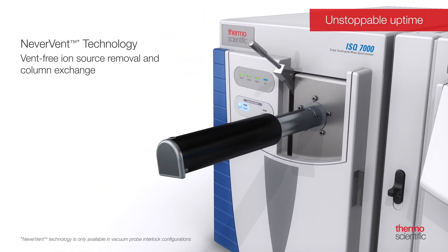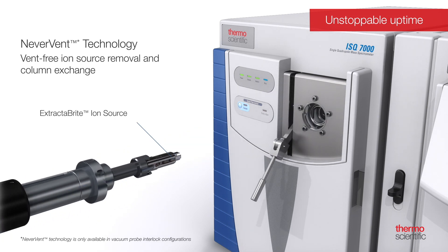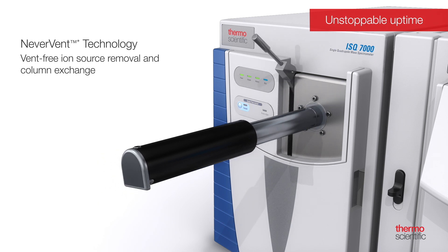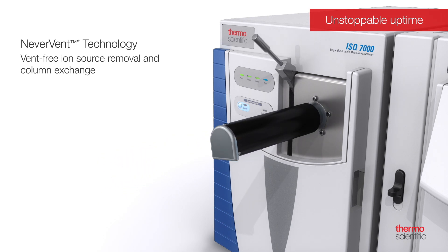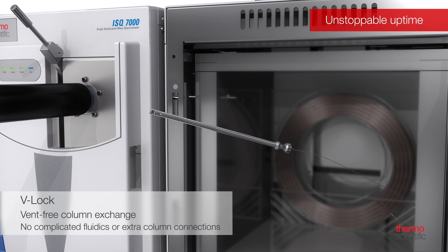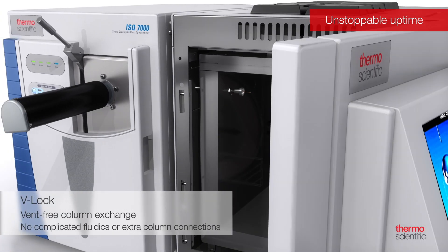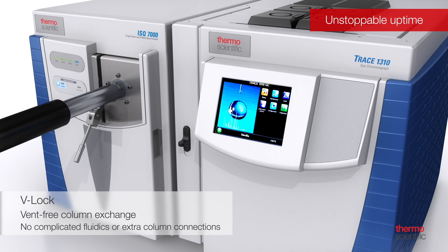The ISQ-7000 single quadrupole system takes your GC-MS uptime to the next level with patented NeverVent technology. Using the vacuum probe interlock in conjunction with the ExtractaBrite source and the new V-Lock source plug, routine maintenance operations such as source cleaning and direct connected column changing can be performed without the need to vent the mass spectrometer. This boosts instrument productivity to unprecedented levels. V-Lock isolates the vacuum region of the mass spectrometer from the column, enabling GC column changes to be performed quickly with no venting required, maintaining a direct connection of the column to the MS transfer line. There are no complicated fluidics with additional auxiliary gases or column unions that can potentially leak.